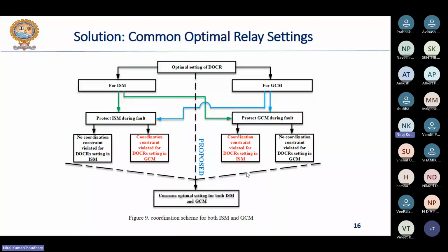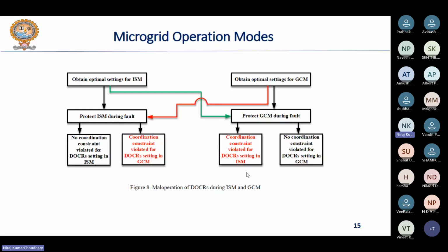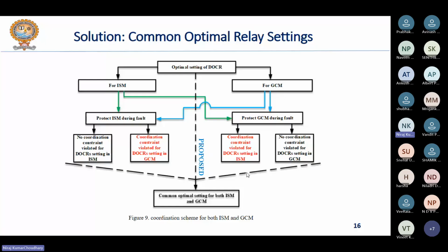Means I want to say that in this previous figure, as we have seen, there was a problem with the coordination of relays when the mode of operation of the microgrid changes from grid connected mode to islanded mode and vice versa, right? So there may always be a change in mode of operation because you don't know about the behavior of the system, how it may behave depending upon the fault in the system towards the upstream network or the downstream network. There may always be a change in the mode of operation due to the transition from grid connected mode to islanded mode. So it is not a good option to calculate the relay settings in isolation for the individual mode of operation. There should be a common optimal setting that is valid for both modes of operation, right?